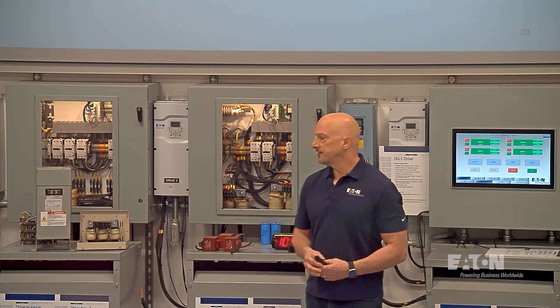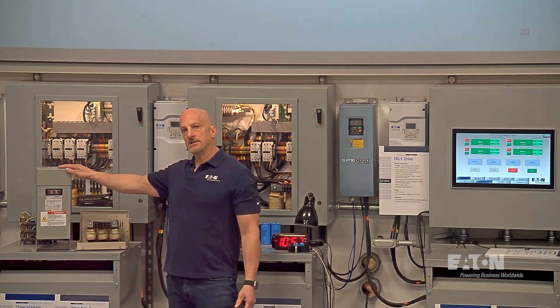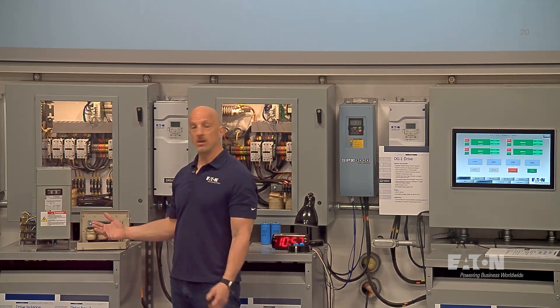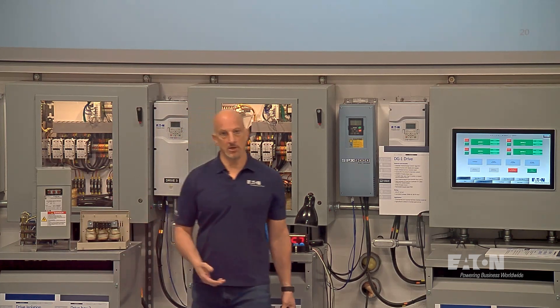If I have these components, for example, if I have a capacitor and I decide one day that I want to switch it into a harmonic filter, all I really need to do is add in a line reactor to make it into a harmonic filter.